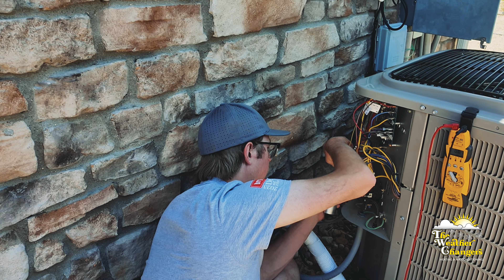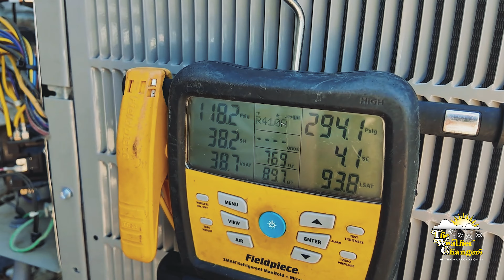All right, we're hooking up our gauges now. We're going to do that to make sure refrigerant levels are normal. Looking at our levels here, both of our saturations look clean. Subcool's right around where we want it. This system looks good. We're going to shut off the AC so we can check the electrical components.